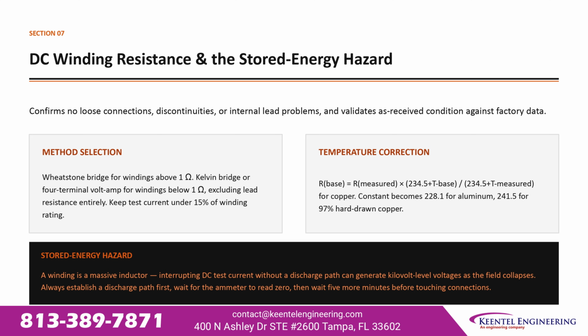Temperature correction matters too. For copper, corrected resistance equals measured resistance times a ratio built from 234.5 plus base temperature over 234.5 plus measured temperature. That constant becomes 228.1 for aluminum and 241.5 for 97% hard-drawn copper.